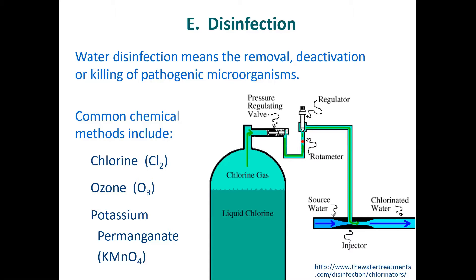Is this the same chlorine that is in swimming pools? Yes. There are different ways to put in the chlorine — traditionally it used to be chlorine gas, which is really bad and very toxic. But most systems now are adding it indirectly, basically adding salts of hypochlorite — usually sodium hypochlorite or potassium hypochlorite. That's the powder you'd see them adding to some pools. At a treatment plant, you scale that up — rather than a scoop, you're talking about giant barrels of these powders. And yes, sodium hypochlorite is basically what bleach is — an aqueous solution of sodium hypochlorite.